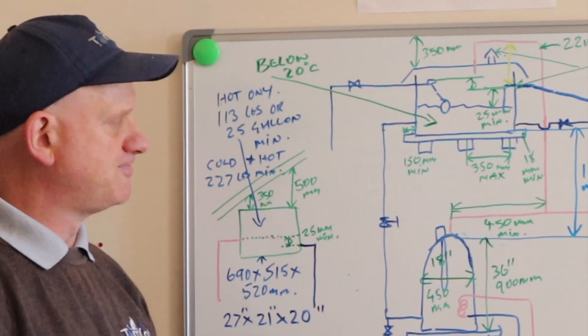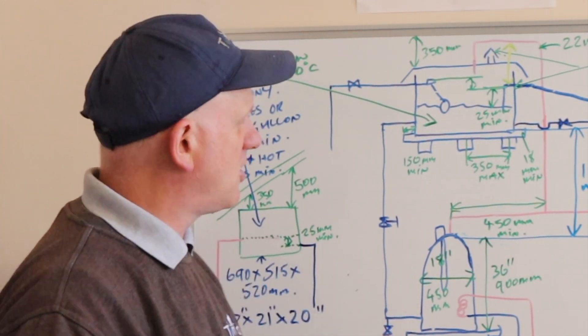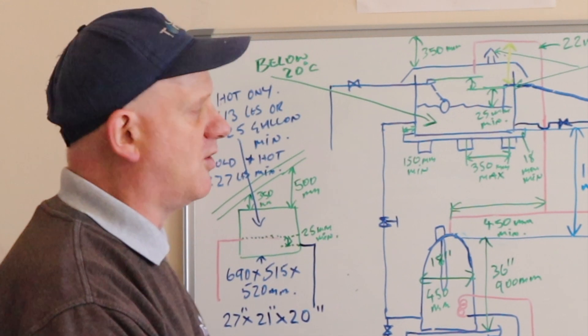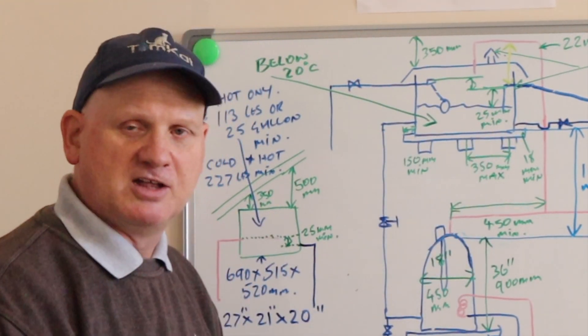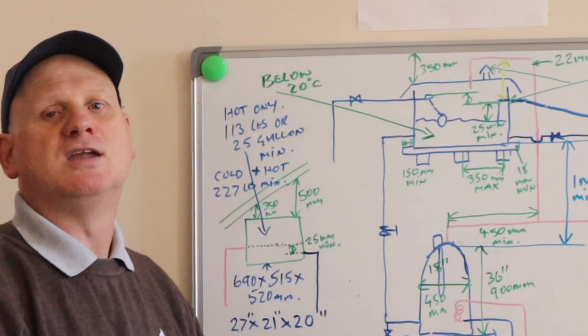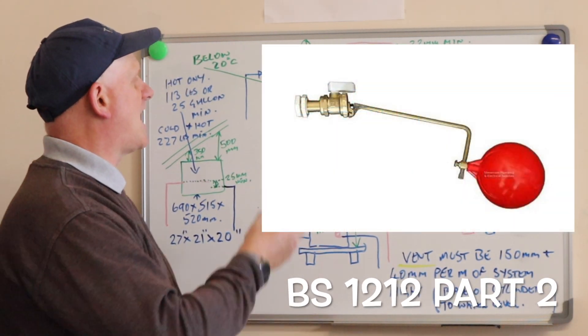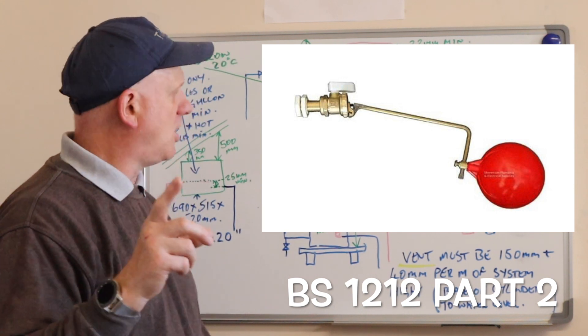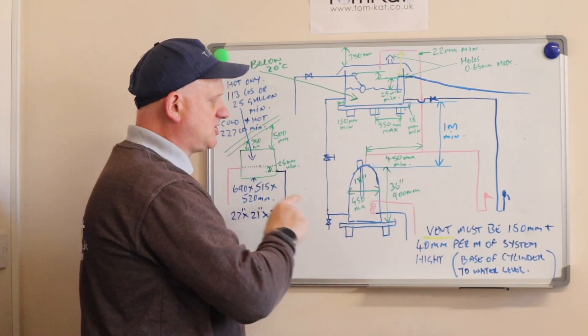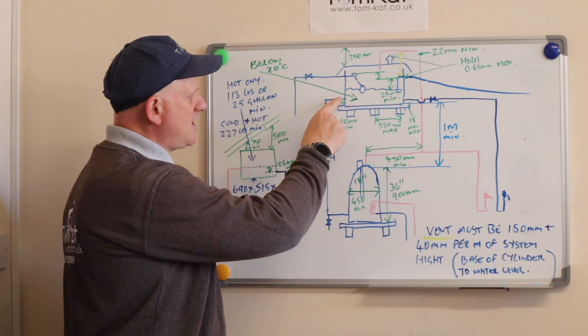The water level is incredibly important and must be set correctly. We have to have a minimum of 25mm from the overflow or warning pipe to the top of the filled system. We also need 25mm difference between the overflow and the top of the float-operated valve. This float-operated valve must be BS 1212, and it has to be a Part 2, not a Part 1.